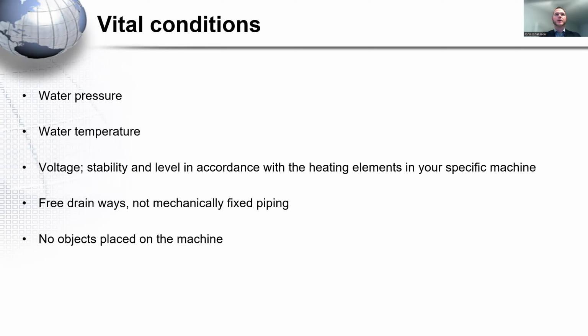So what is very vital is the water pressure, the water temperature, the voltage, free drain ways, and no objects placed on the machine. If we look at the water pressure, first of all, it's regarding how quickly the machine will fill the water into the drum. If you have too low a water pressure, you will have a longer filling time, which will give you a different wash result compared to another laboratory which maybe has the nominal pressure or a high pressure. A high pressure for sure will give you a shorter filling time. Too high a pressure could also cause the machine to have inaccuracy when it fills the water.